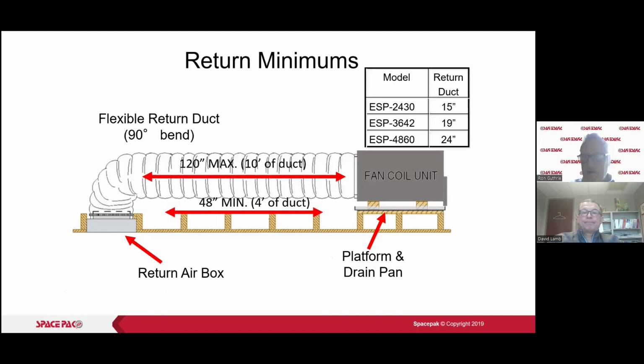Typically we're up on a platform to give ourselves enough drainage. If you look at the return duct there, we've got 15 inches, 19 inches, and 24 inches. So 15 and 19 are odd sizes, but again, we've got the sound attenuation there. Our filter grill is that same size. That gives us the maximum in that oval that we want to put in there. You can make a plenum. You can make an adapter if you want to use 16 inches or 20 inches. Sometimes 24 inches is kind of large and hard to fit. So you could put an equivalent amount of square inch of area, and split that into two returns if you wanted to, and put a plenum box on the end of the unit. So that's possible as well.